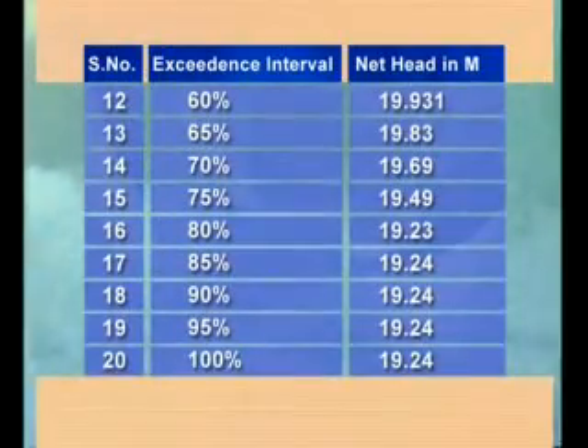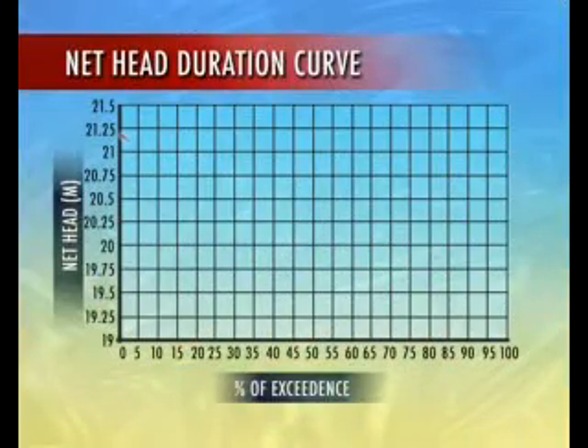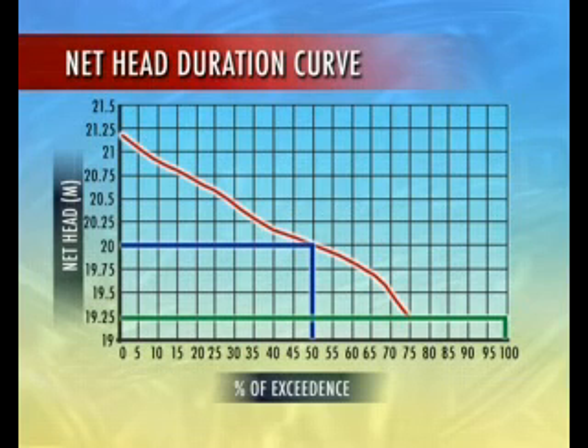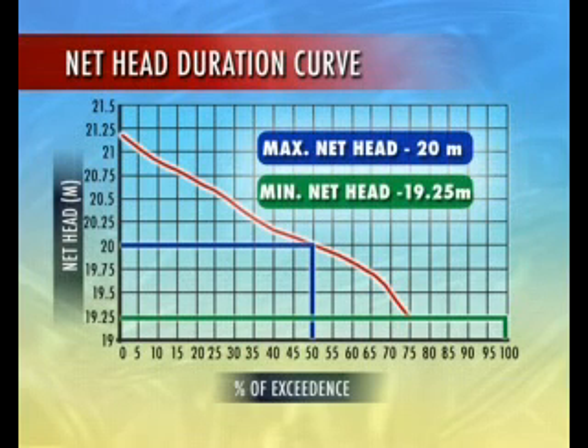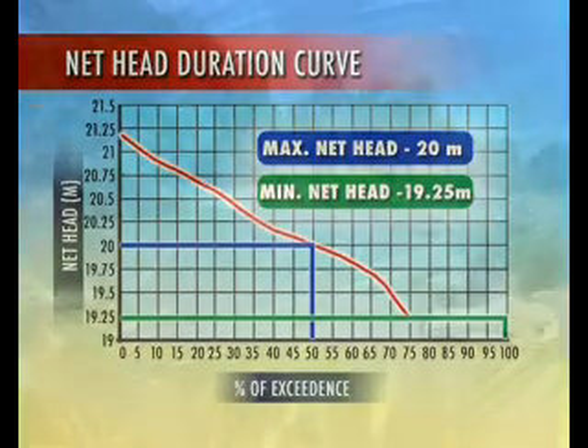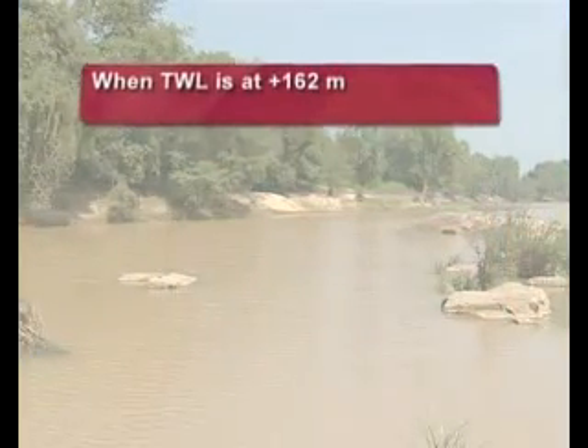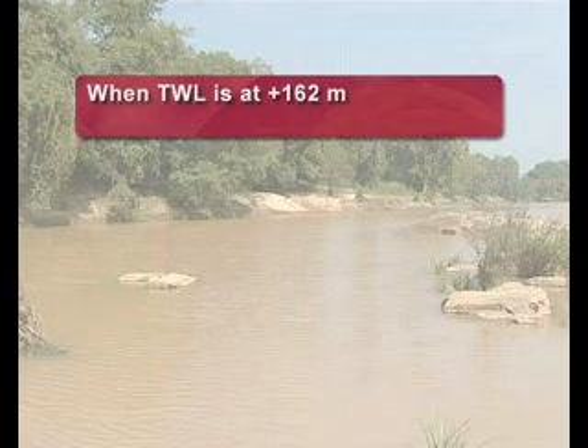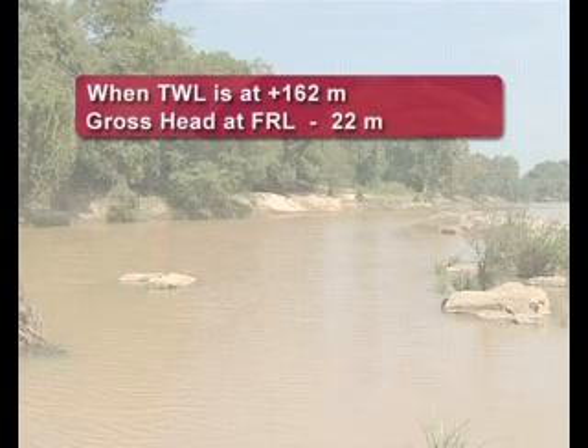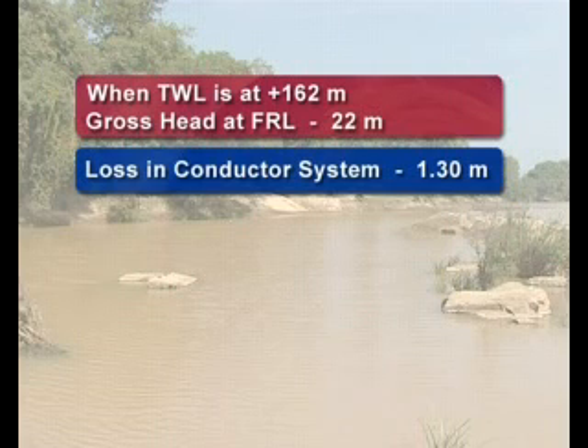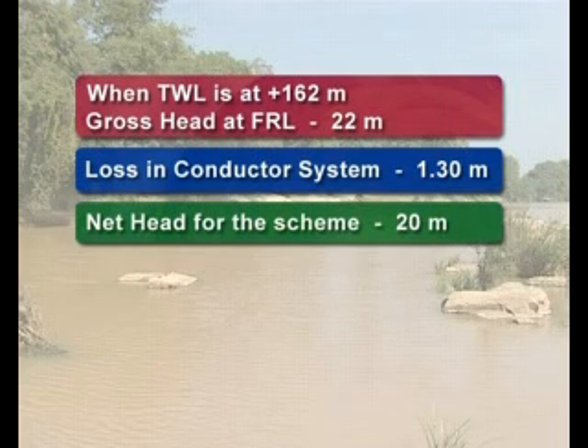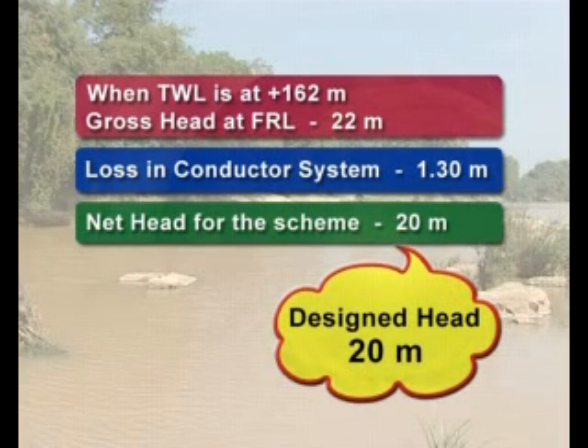Based on these observations, the net head duration curve is drawn. As seen from the curve, the maximum net head and minimum net head are 20 meters and 19.25 meters. When the tailwater level is at plus 162 meters, at FRL conditions, the gross head works out to 22 meters. The loss in conductor system is worked out to 1.3 meters. Deducting the head loss from the gross head, the net head would be 20 meters and the same is adopted as design head for the scheme.